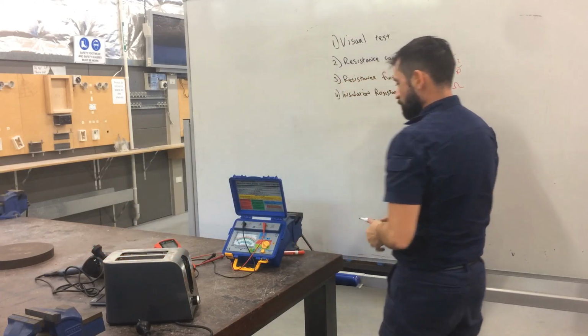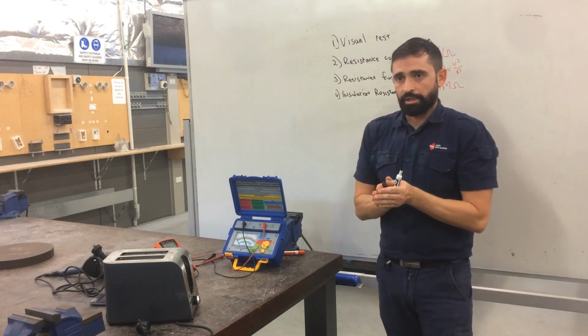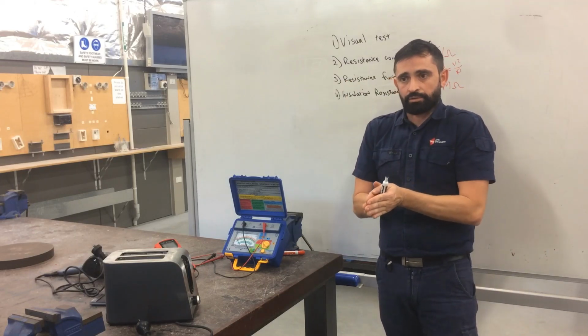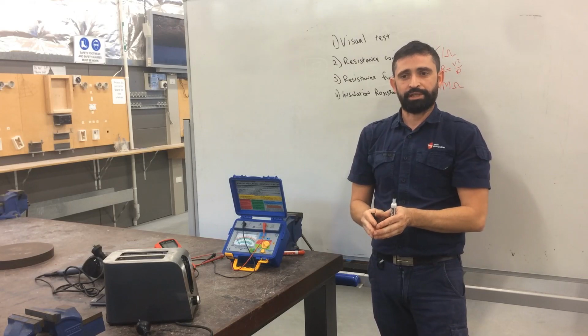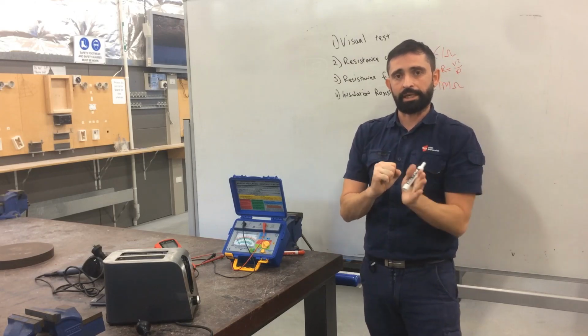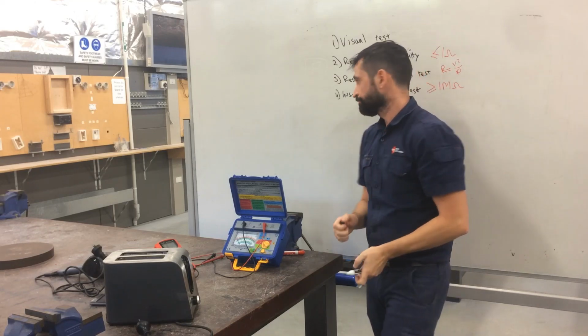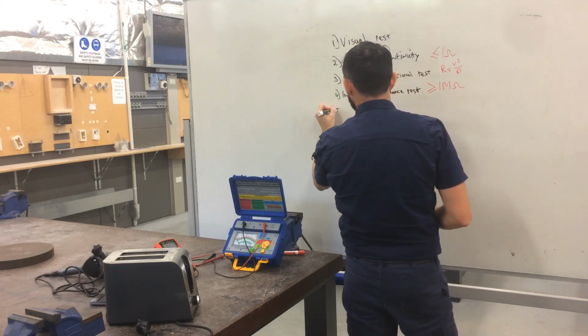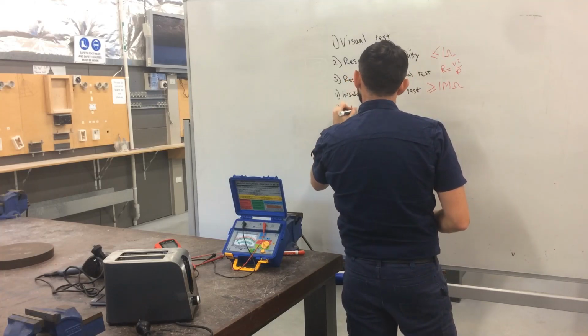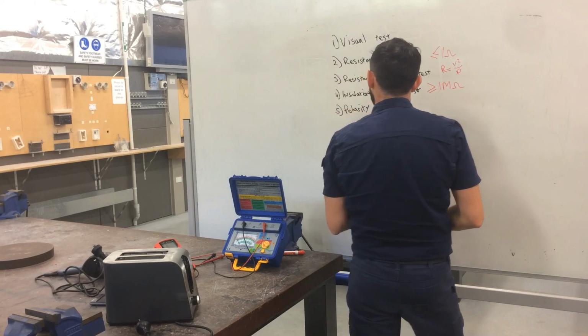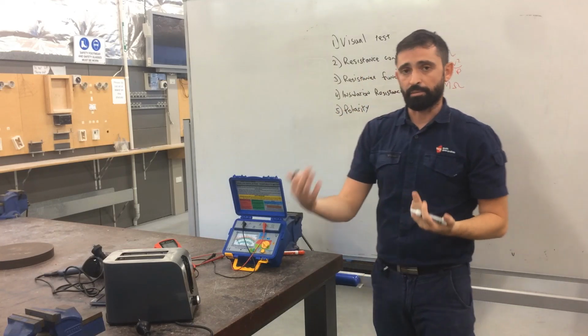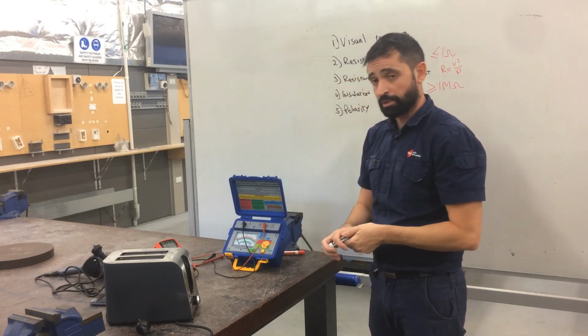So basically we were just determining if the current is going to stay in the conductors where it's supposed to. A bit like a plumber doing a pressure test on his pipe. We want to make sure that nothing's going to leak out. We want to make sure the current doesn't leak out. Alright, and then the final test is the polarity test. However, we couldn't do the polarity test because of the molded plug. Alright, so that's how we do appliance testing.